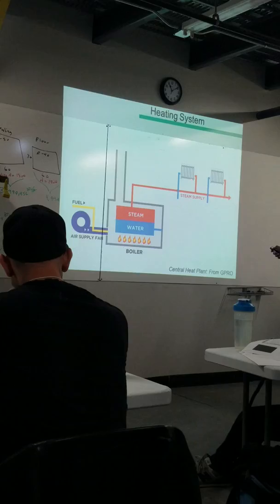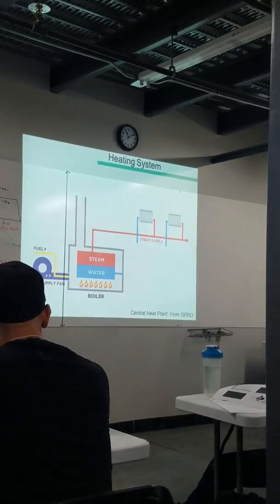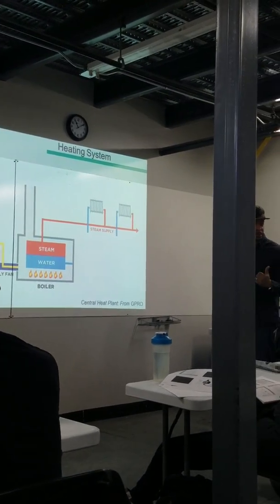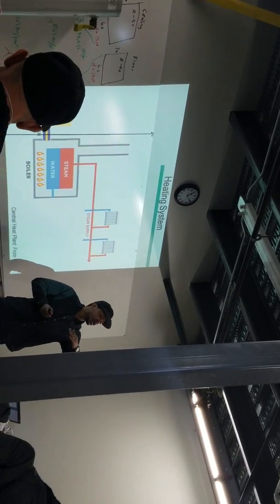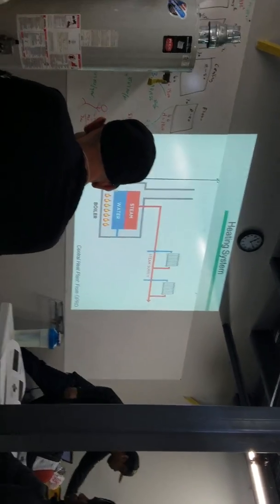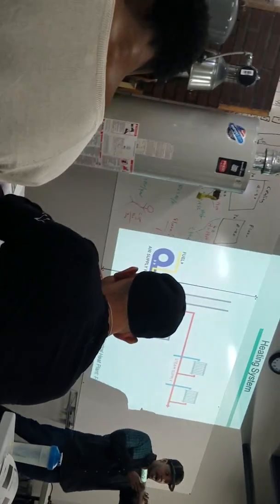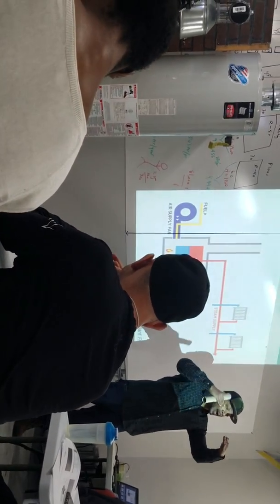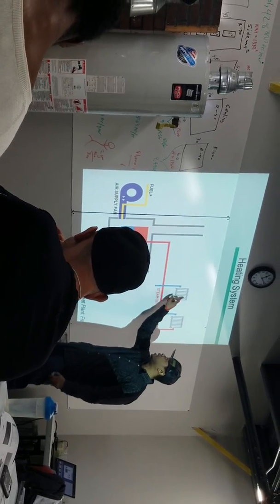The colder it is, steam system. Two pipe because it has two pipes. You have one pipe steam system, right? Where steam and water travel in the same pipe, and it'll be pitched towards what we call the returns. So in a one pipe system, water and steam pass through the same pipe, right? As the steam makes its way, steam rises quite naturally, water's going to be on the bottom. So as they pass, they'll be passing like this. That's a one pipe system. A two pipe system has steam coming in here, it gives up its heat, it condenses, and then it runs back down beneath.